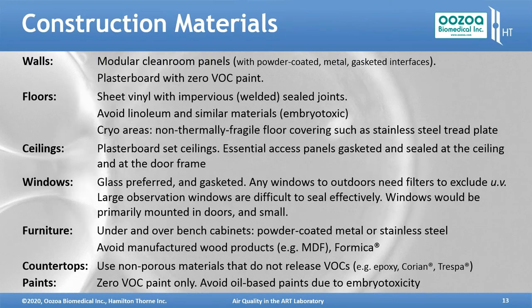In terms of construction materials, for the walls you can use either modular clean room panels or plasterboard with zero VOC paint. For the floors, sheet vinyl with welded joints. Avoid using linoleum and other things like that because they can be embryotoxic. For the cryo areas, where you're going to have liquid nitrogen spilling on the floor, you need to use a non-thermally fragile floor covering, and that really limits you to something like stainless steel tread plate. If you leave bare concrete, then that will still suffer damage, and you may end up having structural damage to the floor in the long term.